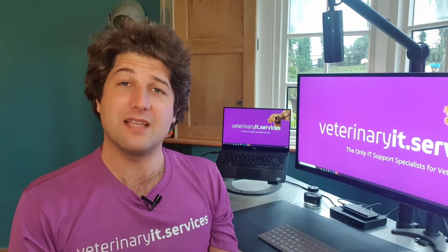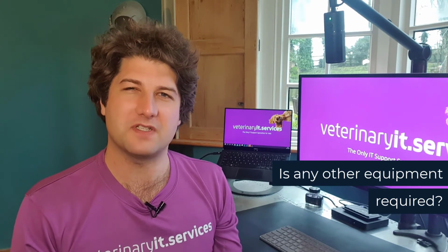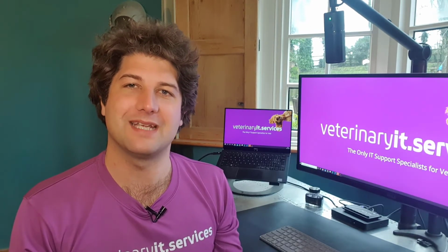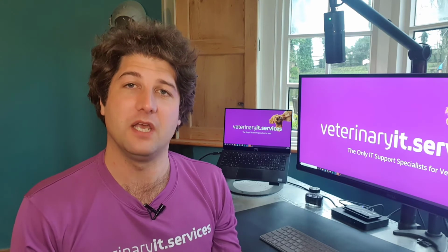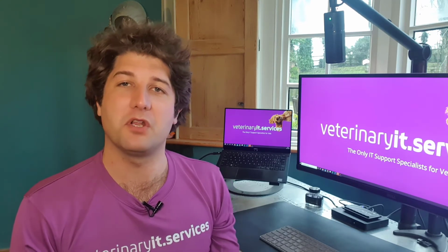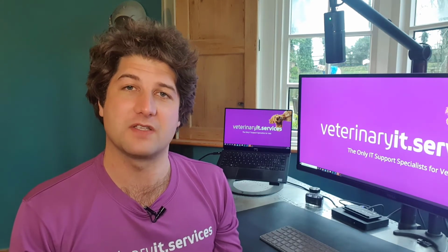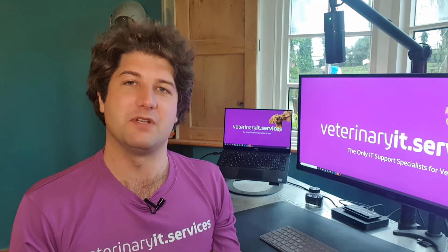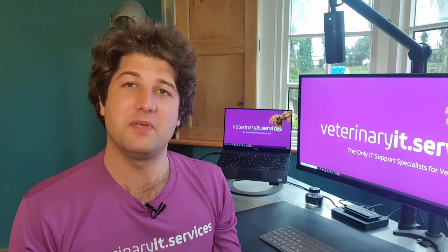Third point, is there any other equipment required? Like with supporting software, you'll need to understand what other equipment you need in place to get the most from the diagnostic equipment, and to ensure that there are no gaps left that need to be filled, as this will have both a monetary and time consequence. Let's again use the example of an imaging device. Will you require storage for the images, and if so, how much? Will it be stored locally on an on-site server, or can it be stored directly in the cloud?